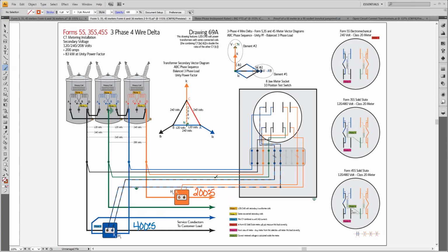And so as we would wire them like this, you'd end up with a 400 and a 200 sitting out there. What would happen with the 400 is we'd see the 400 with 2 turns on it, 1 turn on the blue wire, a 2nd turn on the black wire. So we take our 400 to 5 or 80 to 1 ratio divided by 2, and that would give us a 40 to 1, which is the same ratio as this.